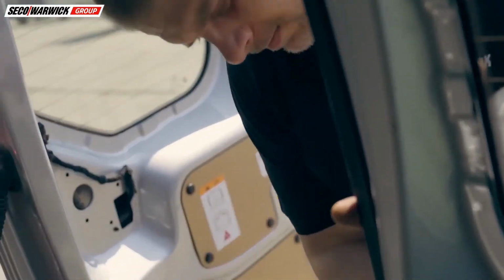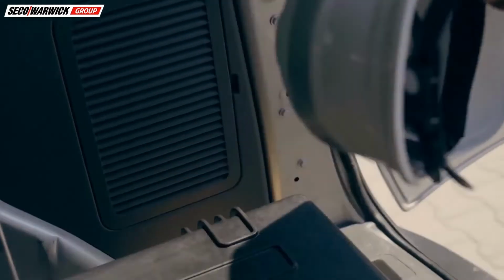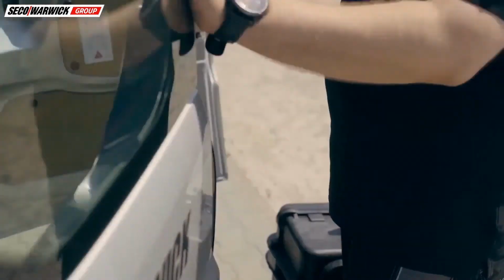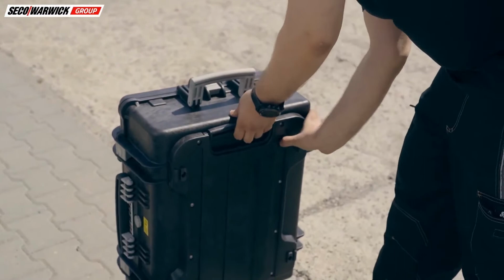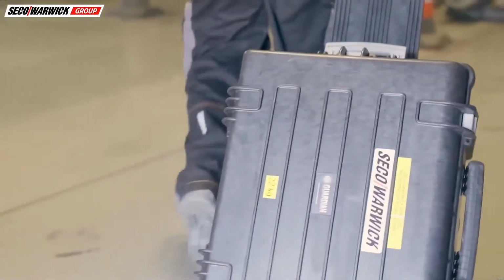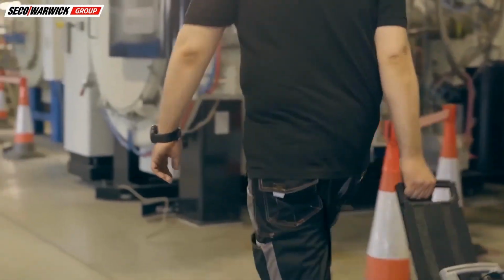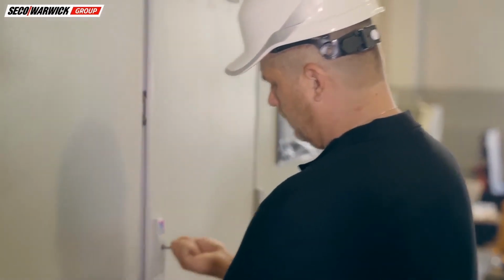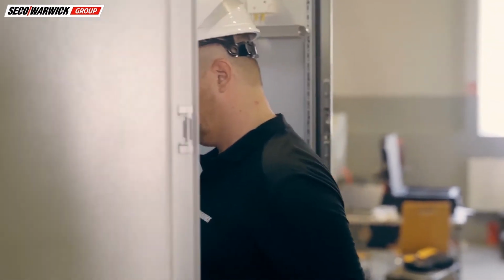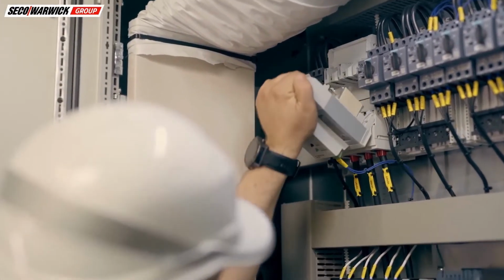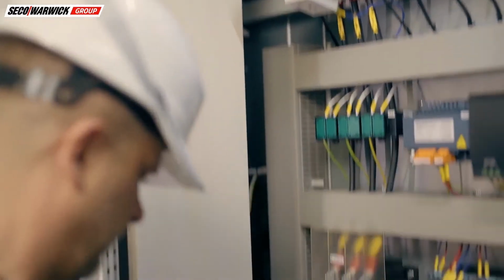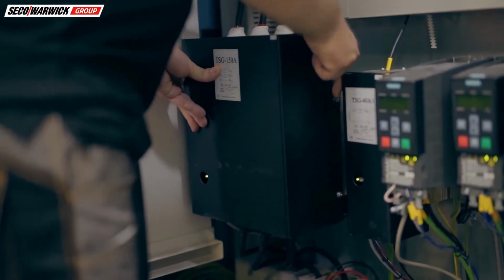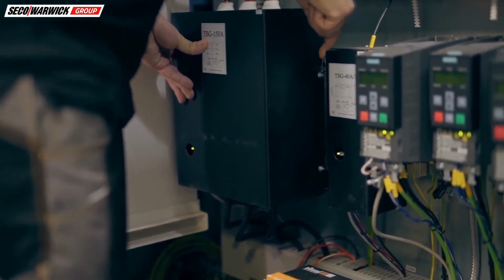Handling of most service requests begins with customer contact and remote verification of important furnace parameters and settings. Frequently the problem can be solved remotely, but in this case it was necessary to send our service engineer on site. After complex remote analysis, the software engineer found out that the cause of the problems is in the heating system, and probably the thyristor or heating controller is damaged. Additionally, the customer asked for a temperature uniformity survey after the repair is completed. Using these 21st century remote diagnostic tools makes diagnosing and solving furnace problems or breakdowns faster than ever before. This also means that we only come on site when absolutely needed or requested to do so. In those instances, we are ready and have the tools and parts needed to fix the issue at hand.